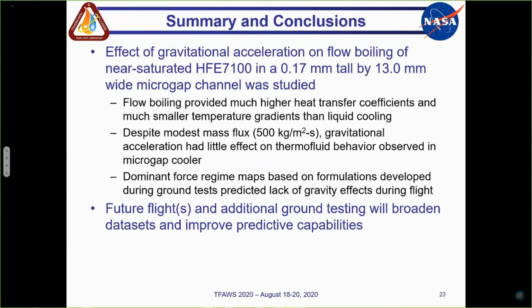We studied the effect of gravitational acceleration on flow boiling of near-saturated HFE 7100 in a 0.17 millimeter tall by 13 millimeter wide microgap. We found that flow boiling provided the high heat transfer coefficients and low temperature gradients we were looking for. Despite the modest mass flux, gravitational acceleration had little effect on the thermofluid behavior in the microgap cooler. However, variation in G did have effects in other parts of the system.